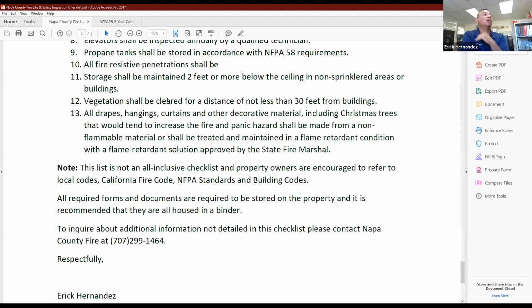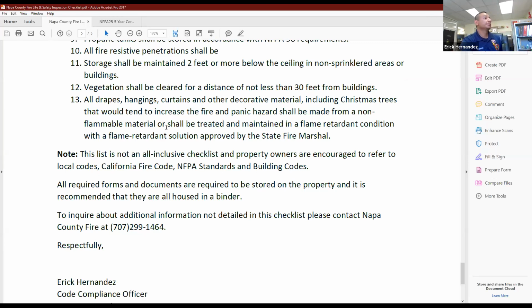Now, if you do have a sprinkler system, it's going to be less. But the whole purpose of the sprinkler system is that not only is it going to wet the walls, but also it's not going to have any obstructions that could potentially prevent it from extinguishing a fire in that particular room.